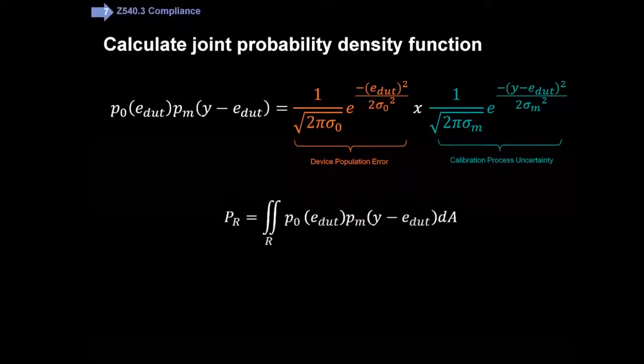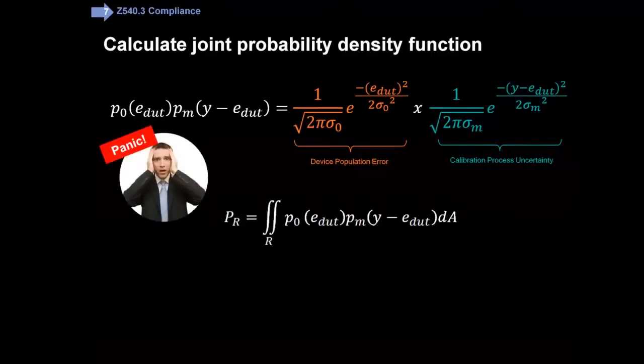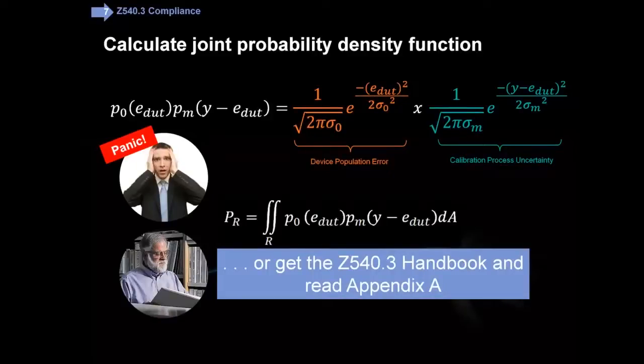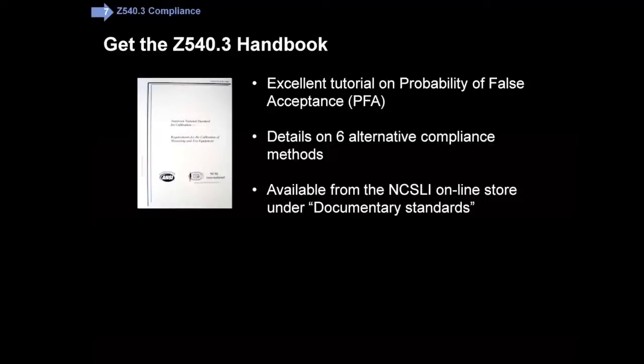There are methods where you can calculate the probability of false acceptance by looking at the probability density function and doing a double integral over the region of interest. When I first read this standard on behalf of Agilent, I had no idea how we were going to meet it. But several years later it's much better, because now you have the Z540.3 handbook. I particularly recommend Appendix A. If you're new to it, go straight to Appendix A. The handbook has an excellent tutorial on the probability of false acceptance and details on six alternative compliance methods, any one of which can be used to comply. There's even a Method 7 that people are working on, but the handbook gives you six choices. It's available from the NCSLI online store.